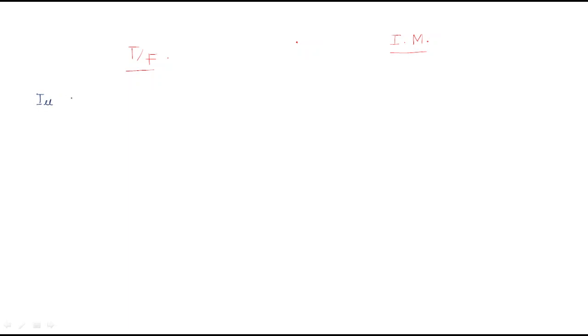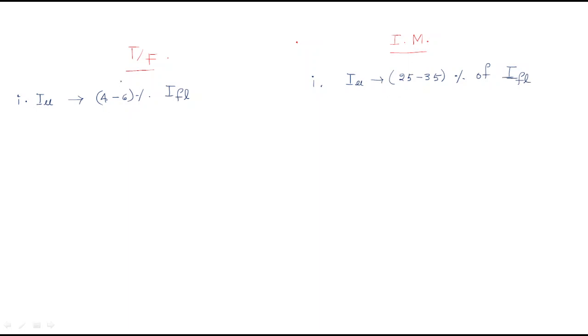The magnetizing current of the transformer is 4 to 6% of the full load current. In the induction motor, the magnetizing current is very high — that is 25 to 35% of the full load current. The transformer requires only 4 to 6% because it has no air gap, whereas the induction motor requires 25 to 35%.